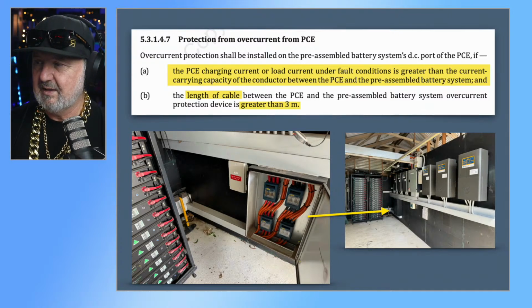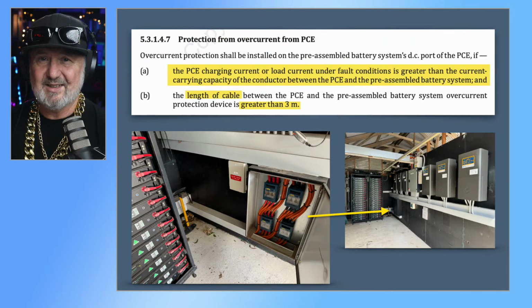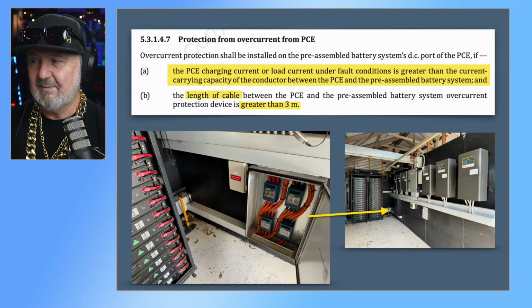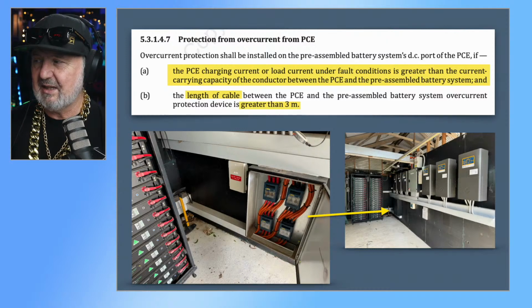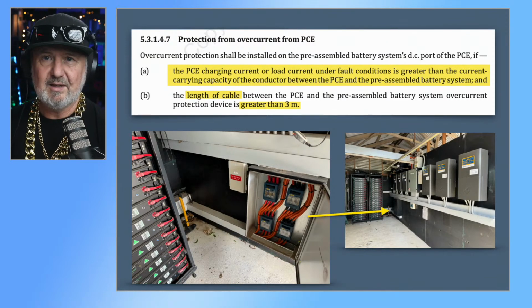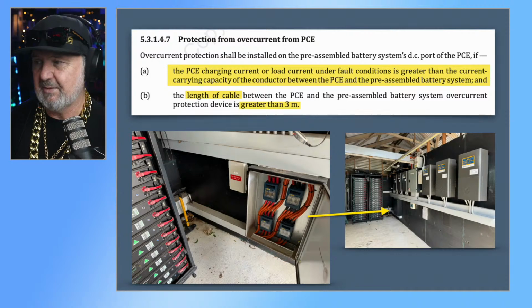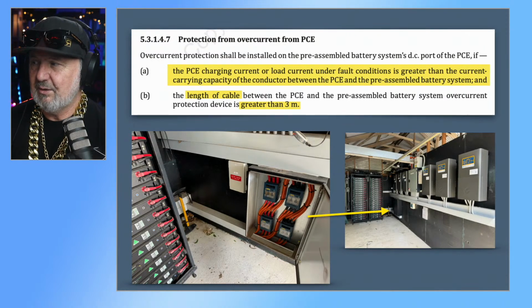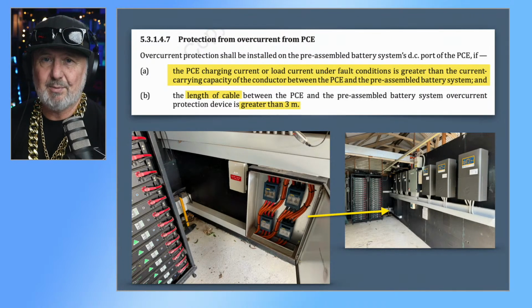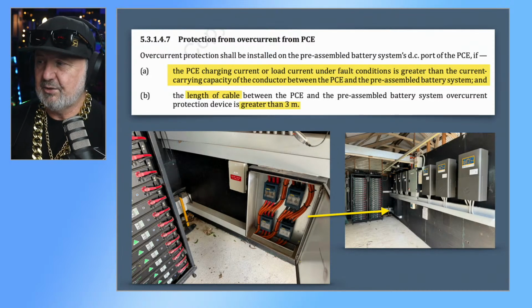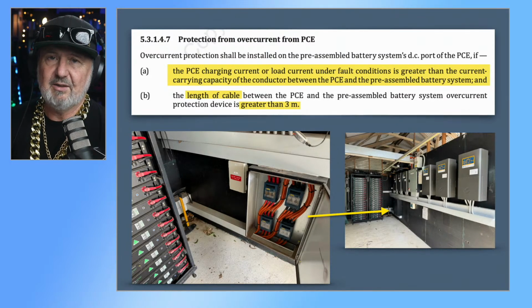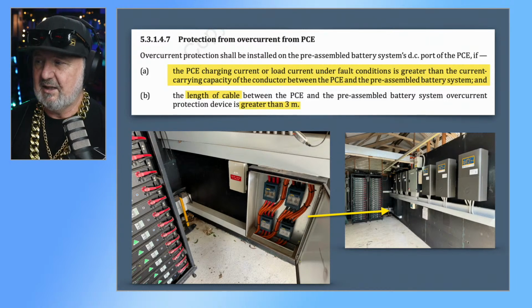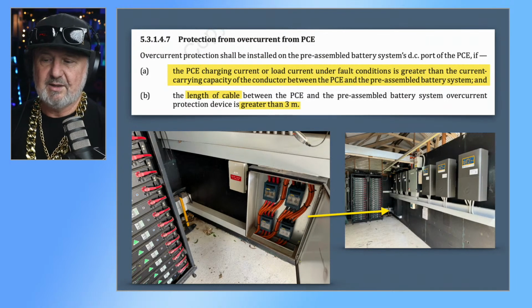When you read a standard that says "and", both of these have to be true before you have to comply. And the length of the cable between the PCE and the battery system is greater than 3 meters. I should say the battery system's overcurrent protection device. So if there's more than 3 meter distance, that's when you need to have overcurrent protection at the PCE, at the inverter. If it's over 3 meters and it can source a higher current than the cable's rated for. So there you go. So it's another source.